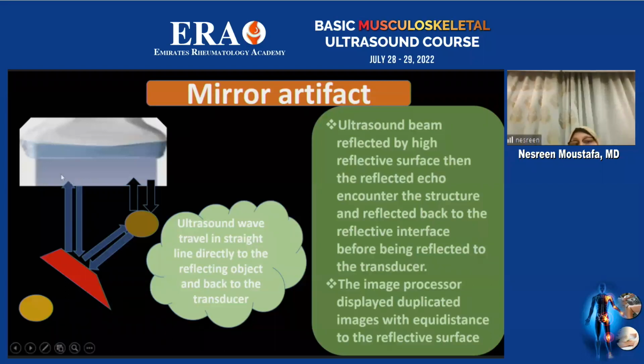What happens is the ultrasound beam goes down to, suppose, a bony part, and then an object here. Part of the waves, part of the echoes, return back to the transducer. This makes the primary target. After that, the beam goes around to a secondary object and strikes it, and that echo returns, but very late. So that echo will appear a little bit deeper and will appear beyond the reflector.